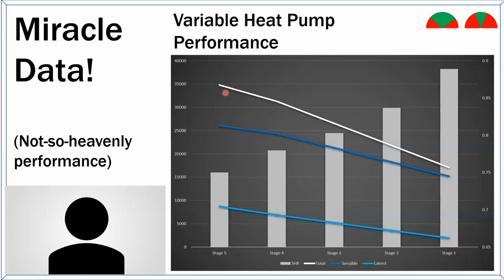And if you look at the total capacity, it falls pretty steadily. If you look at the sensible capacity, it falls less - these are further apart than these are, this slope is lower. And if you look at the latent capacity, it falls more steeply. What are these bars? These are the sensible heat factors, sensible heat ratios of the equipment.